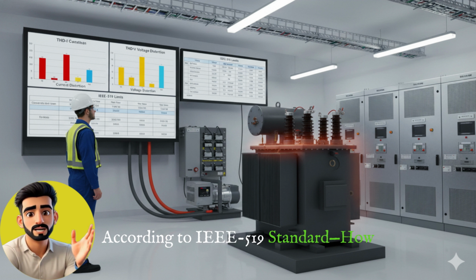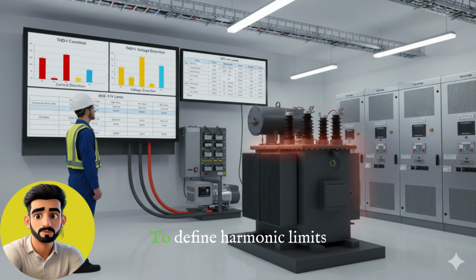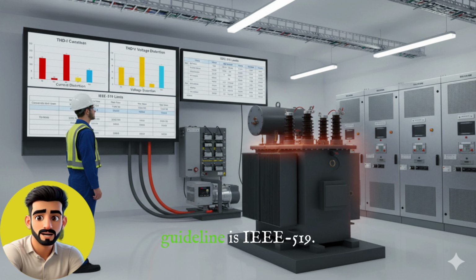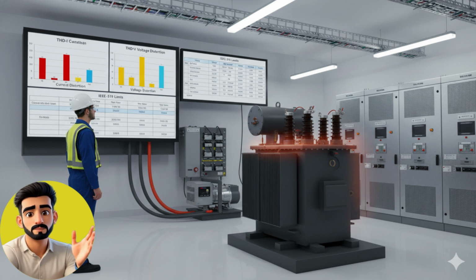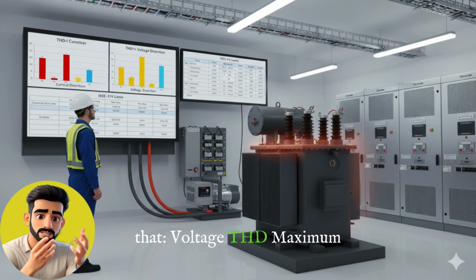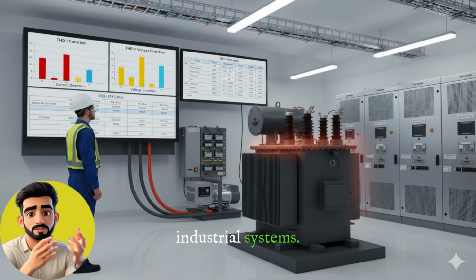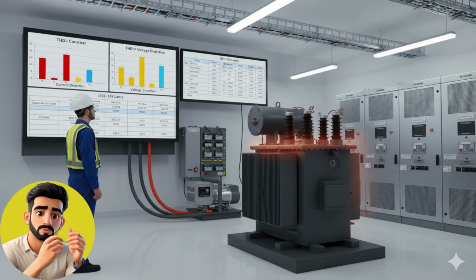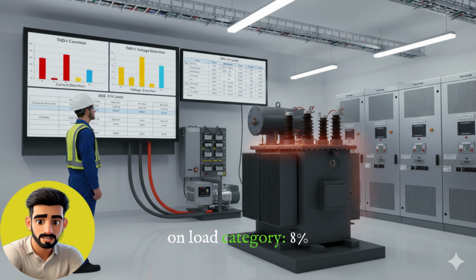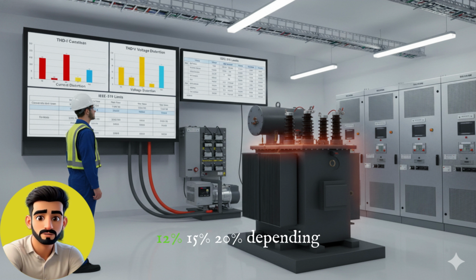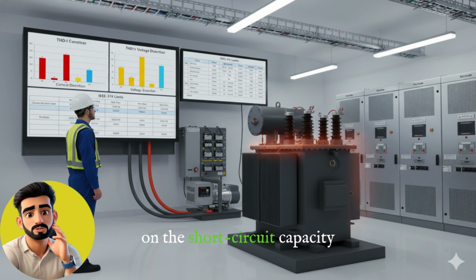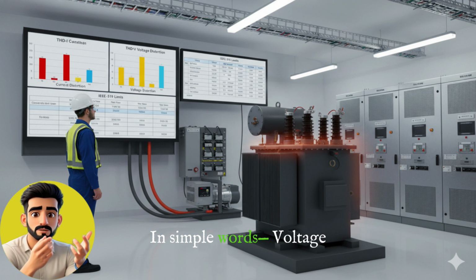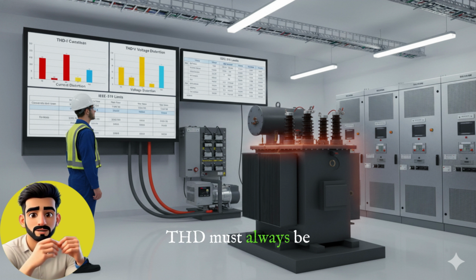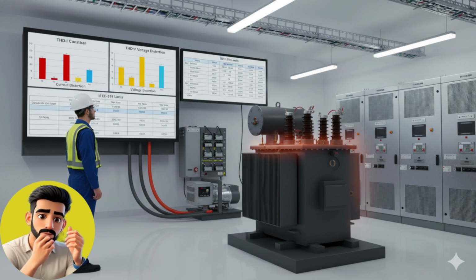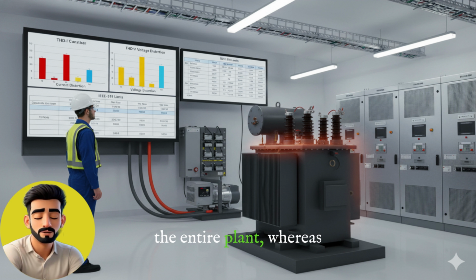According to the IEEE 519 standard, how much THD is allowed? To define harmonic limits worldwide, the most trusted guideline is IEEE 519. This standard clearly states that voltage THD, maximum 5% allowed in most industrial systems. In critical systems, this limit can be more strict. Current THD limits depend on load category: 8%, 12%, 15%, 20%, depending on the short circuit capacity of the system. In simple words, voltage THD must always be kept low. Current THD is allowed a bit more. Because voltage distortion impacts the entire plant, whereas current distortion is mostly handled at the source level.